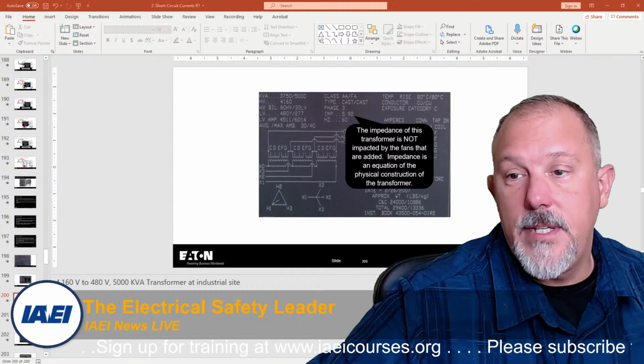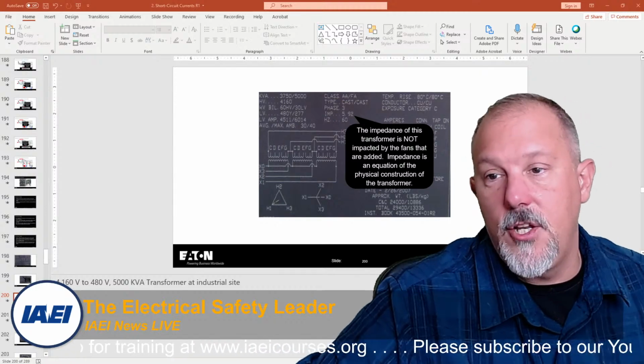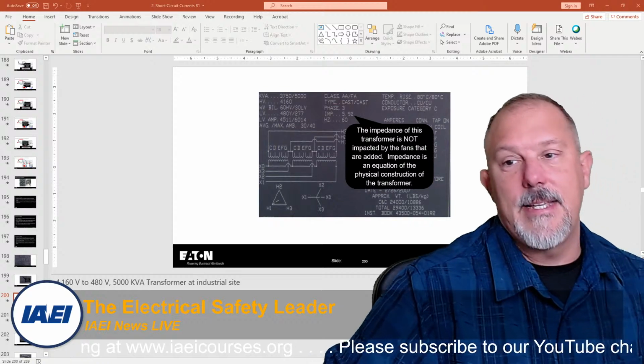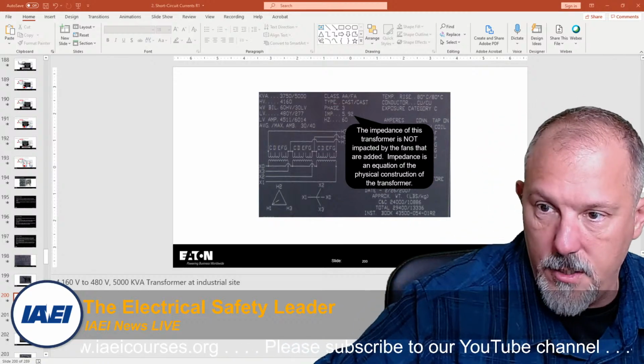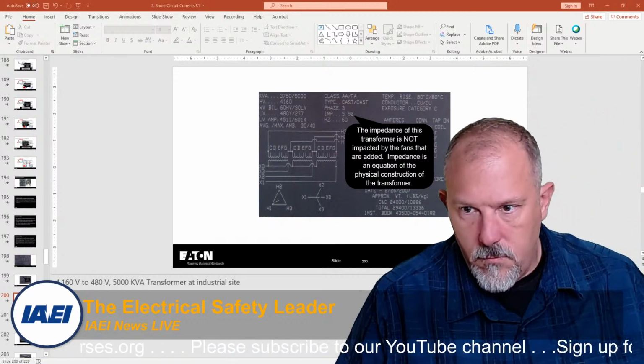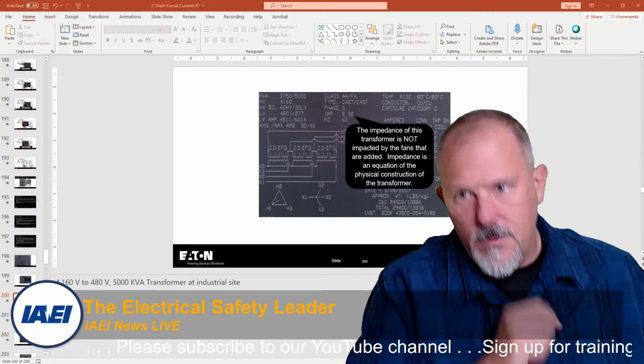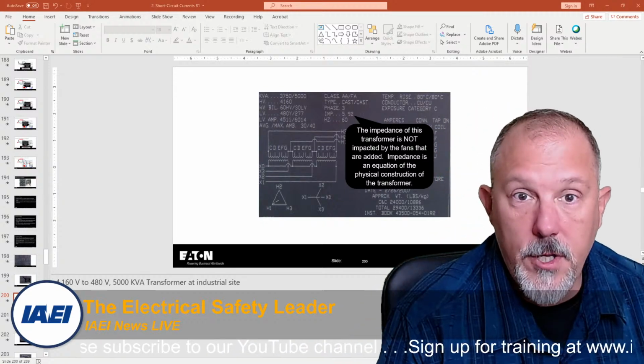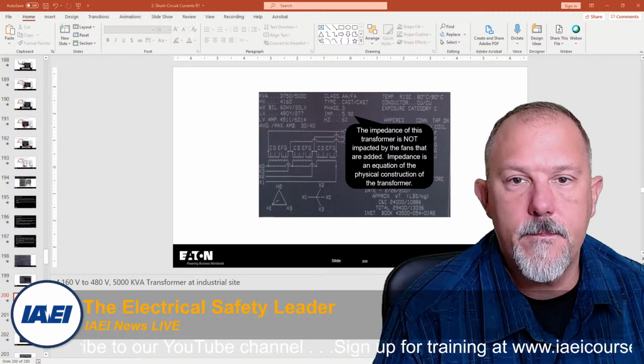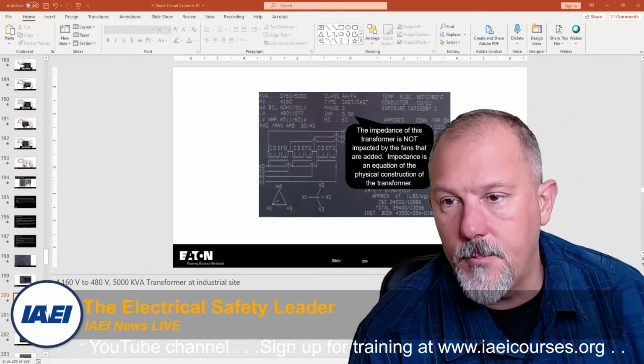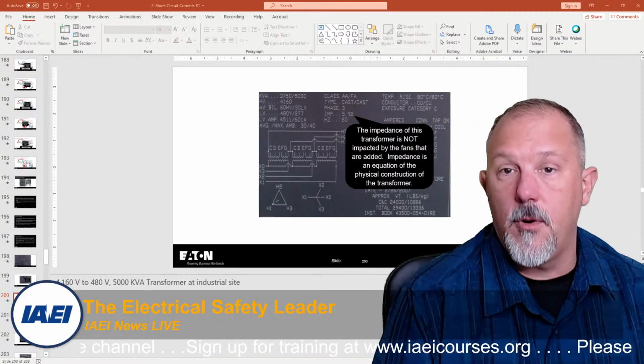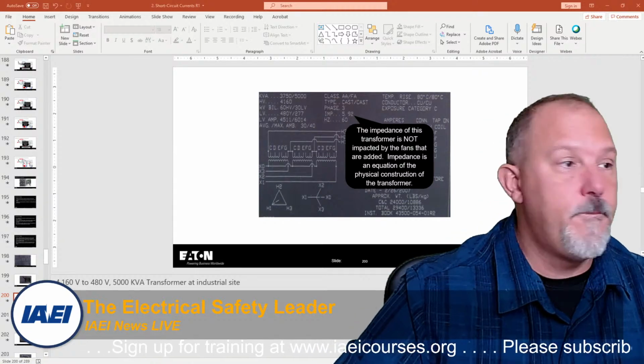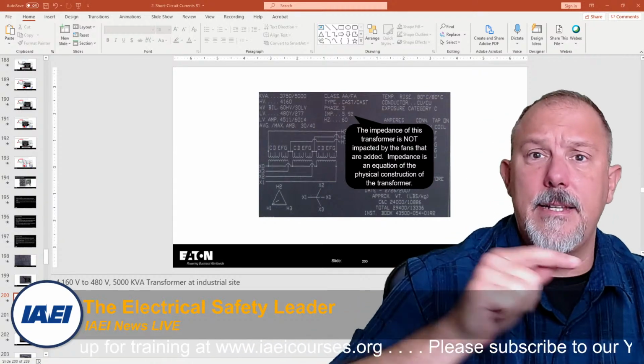Oh, so he says, I understand the fans make no difference. What he's asking is, how do we conclude that the percent Z is based on the lower kVA marking? Because that's how it's listed and tested.